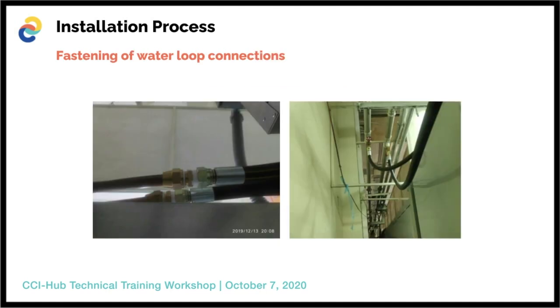Then the fastening of water loop connections. Once the R290 showcase was fixed into position, we then connected both the in and the out connections of a heavy duty flexible hose from the pipe duct valve into the heat exchanger of the showcase. The main pipe had already been circulating a water and glycol mixture, and these connections must be properly tightened using teflon tapes.